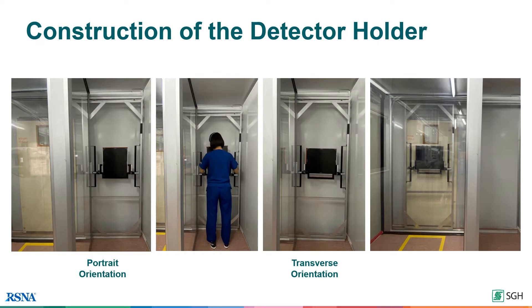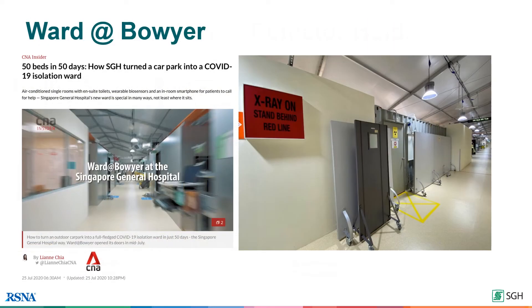Due to the space constraints that come with using a standard container, the detector holder was re-engineered onto a sliding rail system. This allows the radiographer to adjust the height and orientation of the detector according to the patient's height and habitus. Due to the evolving COVID-19 situation, we have redeployed this unit to our new isolation facility, Ward @ Bowyer. Now let us watch a video on how this entire setup works.